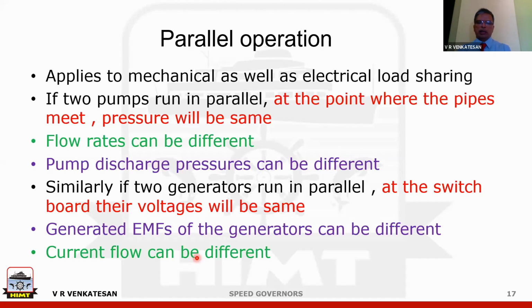So when two alternators run in parallel, it is all right for them to have different current values, but they will always have same terminal voltage. They can also have different EMF. So EMF in the generator is different, terminal voltage is something else. And parallel running machines must have same terminal voltage. And it is not a difficult principle to understand if you think of pumps running in parallel. It is very similar.